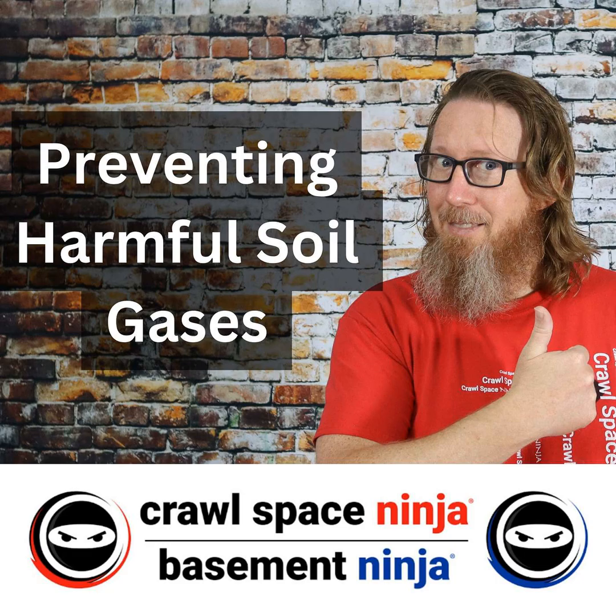What we do is take a Lomanco PCV1 fan — it's about 110 CFM — put it in one of the foundation vents, seal all the others, and have the air blow out all the time, 24/7, even in the winter. The crawl space is sealed so well that the temperature isn't going to change with how we encapsulate and properly insulate it. The Lomanco PCV1 fan does have a built-in switch where if it gets too cold in the crawl space it will shut off — around 35 degrees. But none of our encapsulated crawl spaces typically get below 60 degrees because most of the time HVAC ducts are also pumping heat in there.